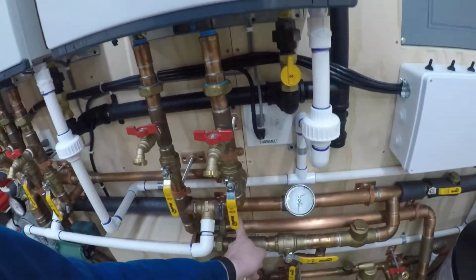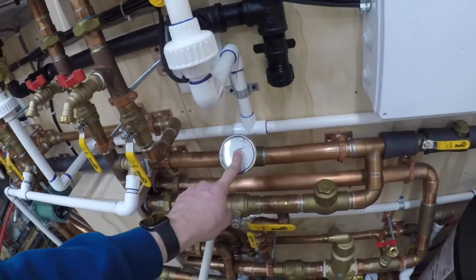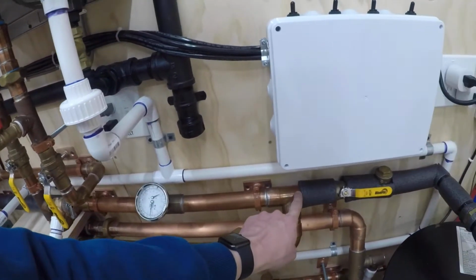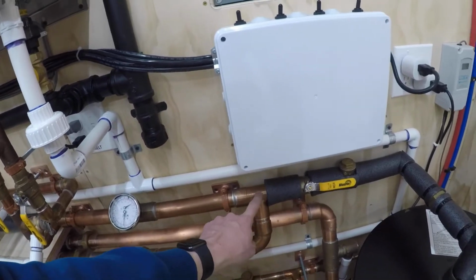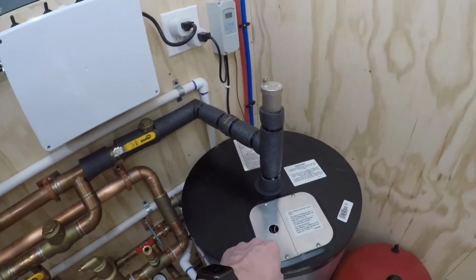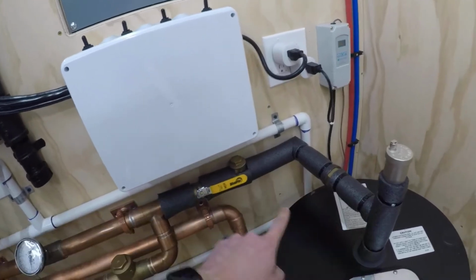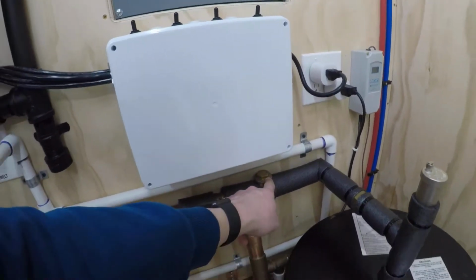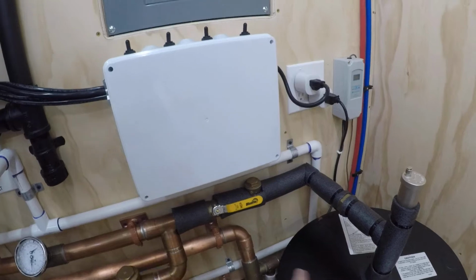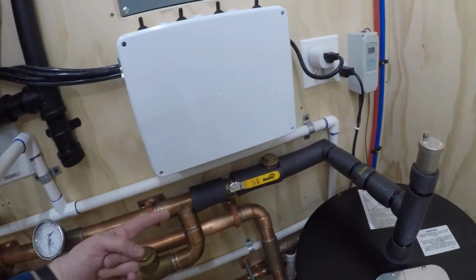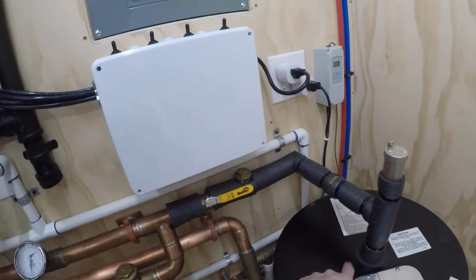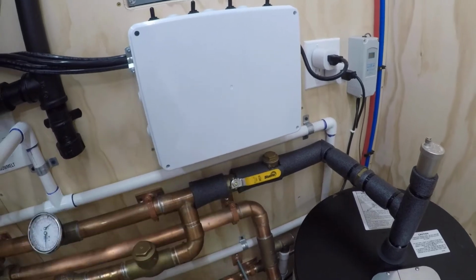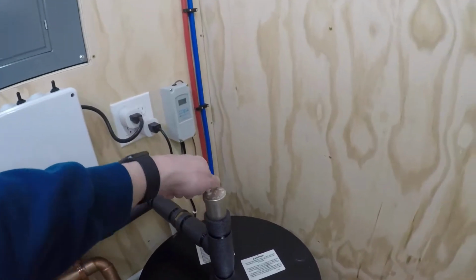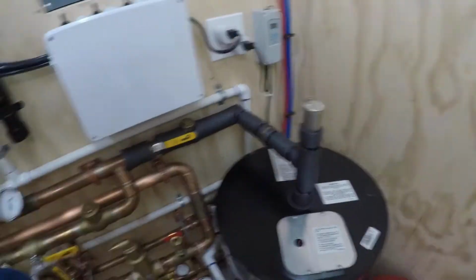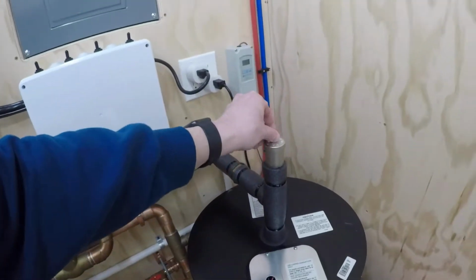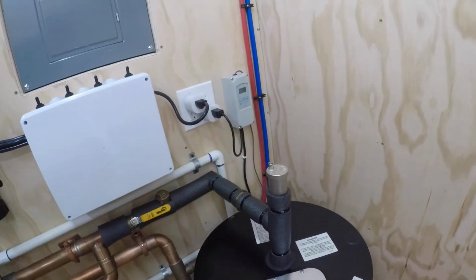Goes into 1.5 here, temperature and pressure gauge, comes over, and this is where it tees to feed the hot water tank. This is all 1 inch here, and there's another check valve here so that you can't get water going the wrong way back into the system. Hot water can go in at 140 degrees, but it can't come out up here. This is just an air vent. Any air that might come in from the street and get into the tank bubbles up and it automatically bleeds itself out.